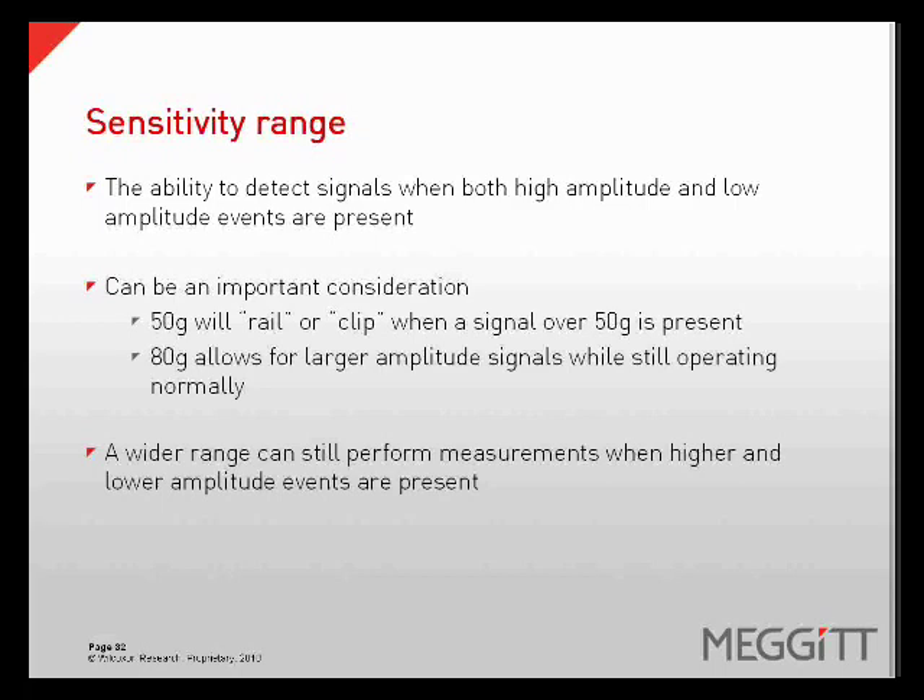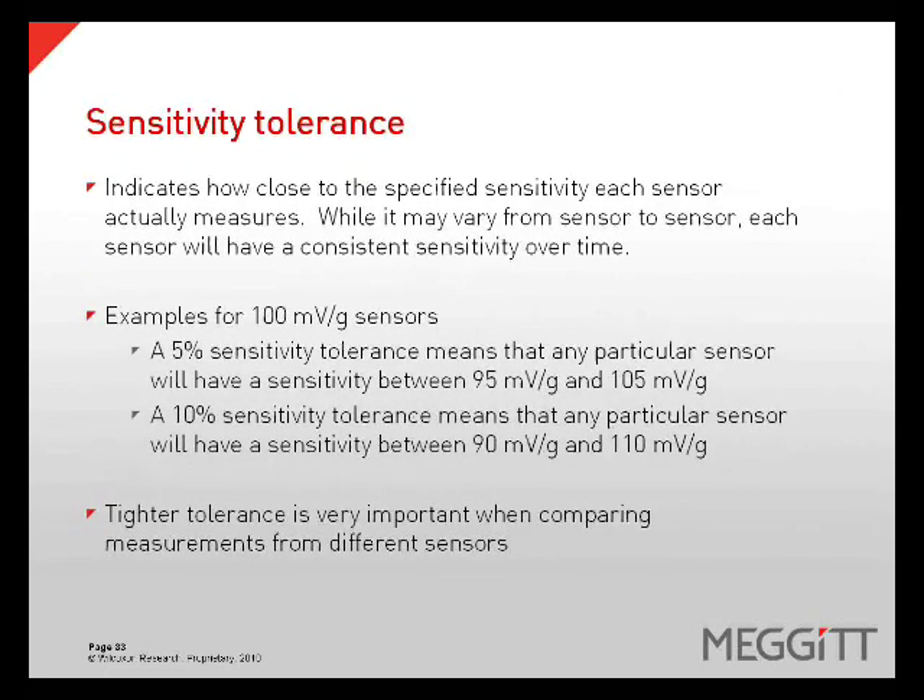Sensitivity range is the sensor's ability to measure lower amplitude signals when a high amplitude event is present. A 50 G sensor will rail or clip if an event exceeds 50 Gs, while an 80 G sensor allows for normal operation with much higher amplitudes present. A wider range lets us measure lower amplitude events when high vibration is occurring. Sensitivity tolerance is how close to a specified sensitivity a sensor actually measures or outputs. A sensor with a 5% sensitivity tolerance specified to output 100 millivolts per G must output between 95 and 105 millivolts per G. Tighter tolerances are important when comparing measurements from different sensors.